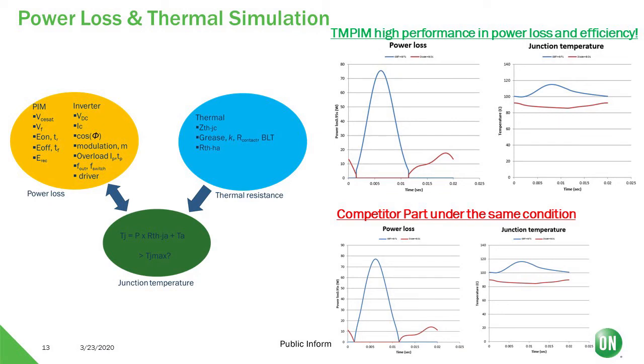Based on the DC and AC data, we can simulate the power loss of the module at a given working condition. The DC data will be used to calculate the conducting loss, using voltage drop multiplied by the current. The switching loss occurs at each switching moment. By accumulating the power loss at each moment, we can find the total power loss of the device. At the same given working condition as shown in the chart, TMPIM has slightly lower power loss and higher efficiency.